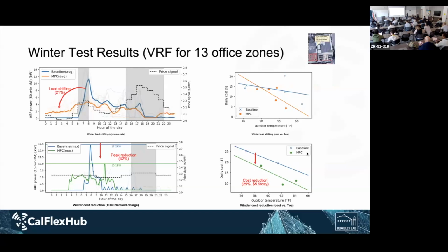The building, the photo is very small, but it's located in Davis, and it's composed of 13 office zones, with one VRF system handling conditioning for the whole space. We developed the MPC last year for coordinating the heat pumps, and we modified the objective function a bit and extended the heat pump MPC to the VRF, and thankfully it's working okay.